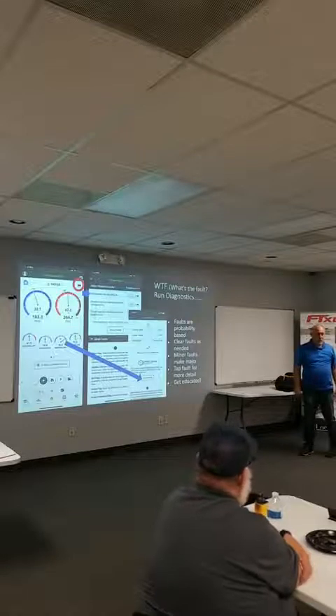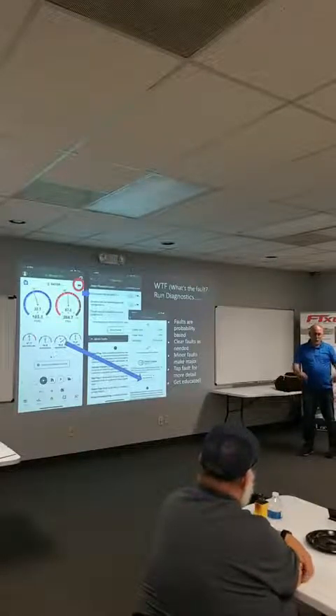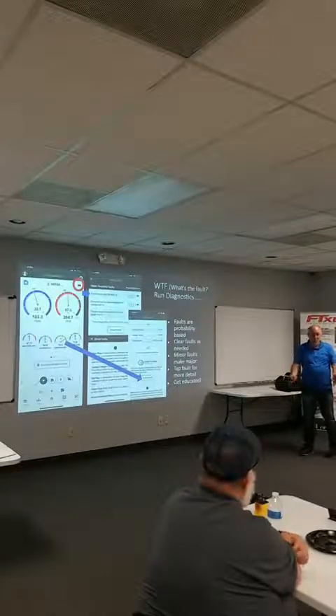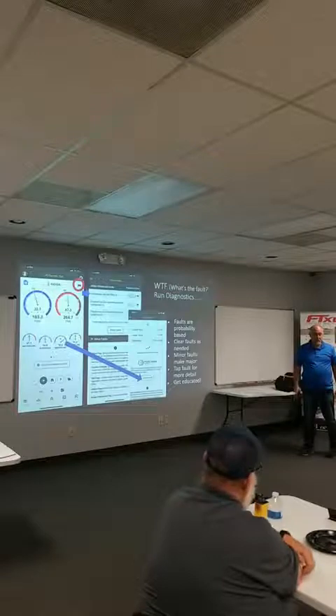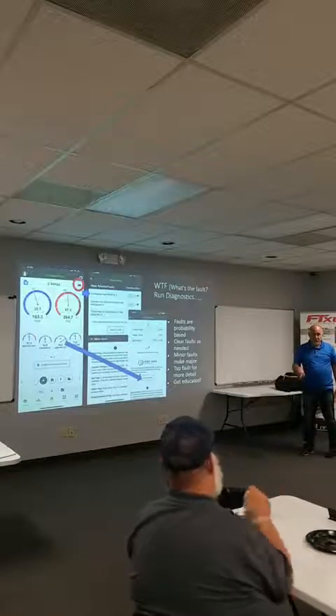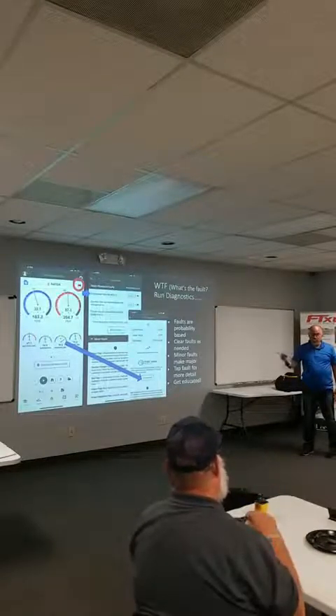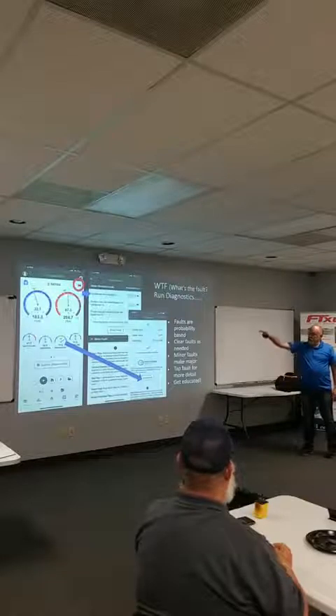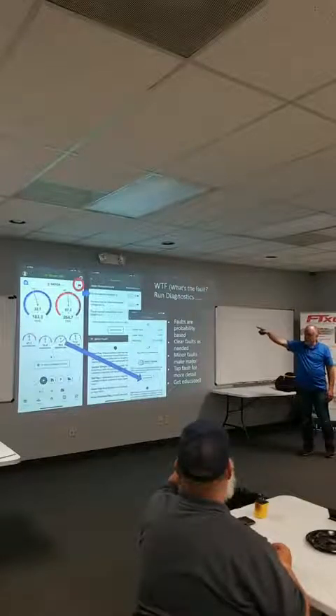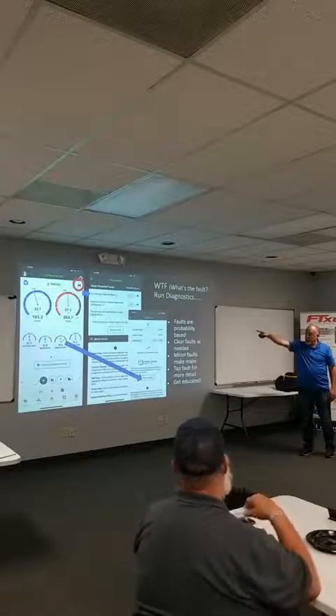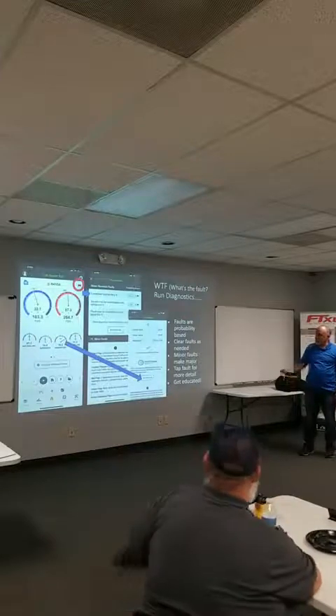So what's the first thing somebody's going to do? They're not going to look at the condenser, they're going to start dumping gas out of the machine. Oh, it's overcharged. Did you look at the condenser? You just split it apart and see if it's dirty in between, right? Because this is the kind of stuff people do all the time, and they figure somebody just overcharged it without taking a look to see if it's actually dirty. So when it says the condenser may be dirty, that means you need to look at it. Or it could have an overcharge, or it could be a restriction of the liquid line, right?